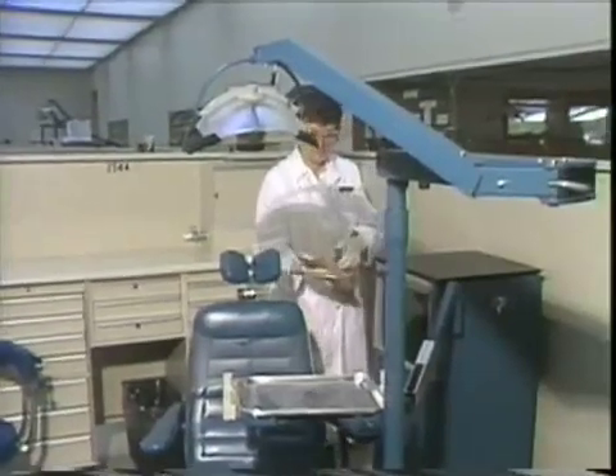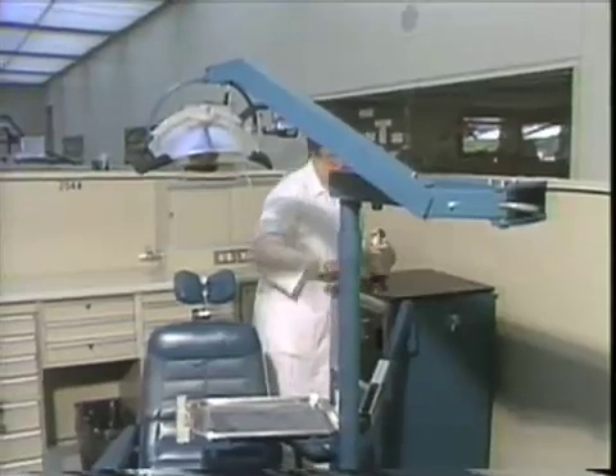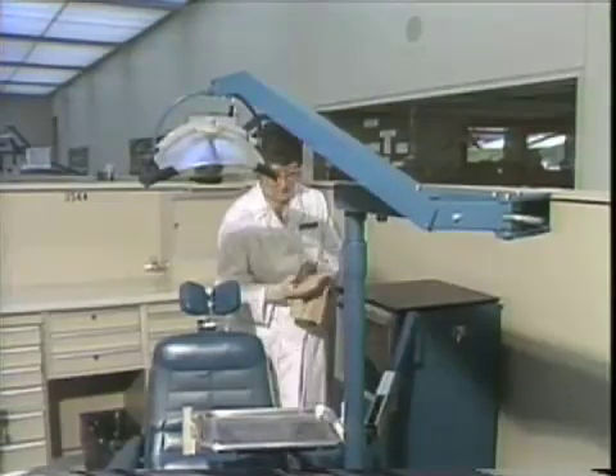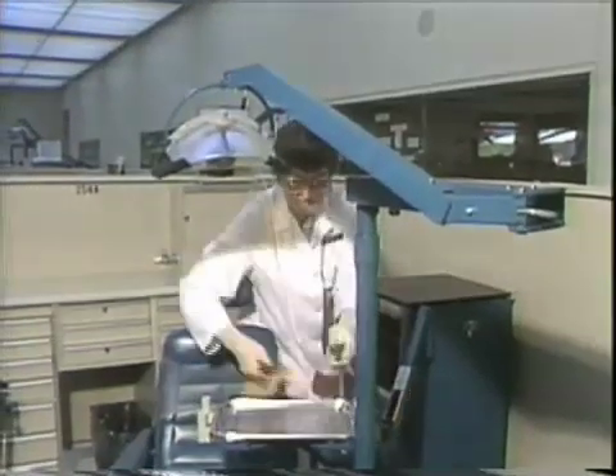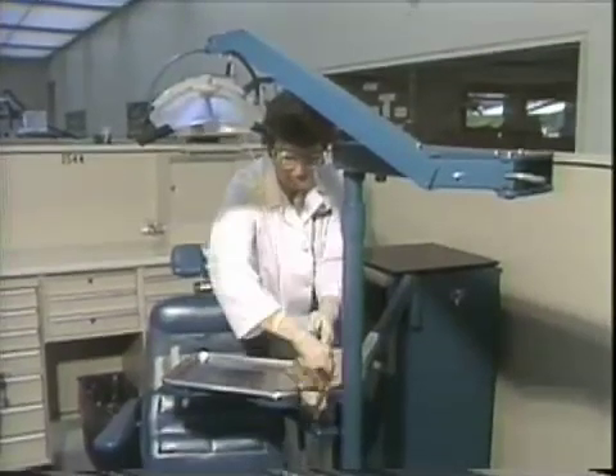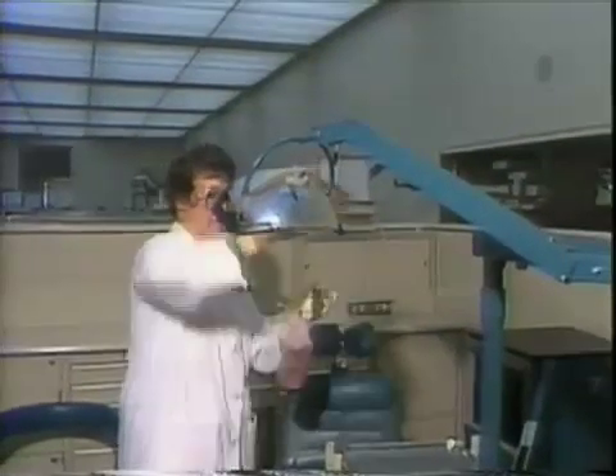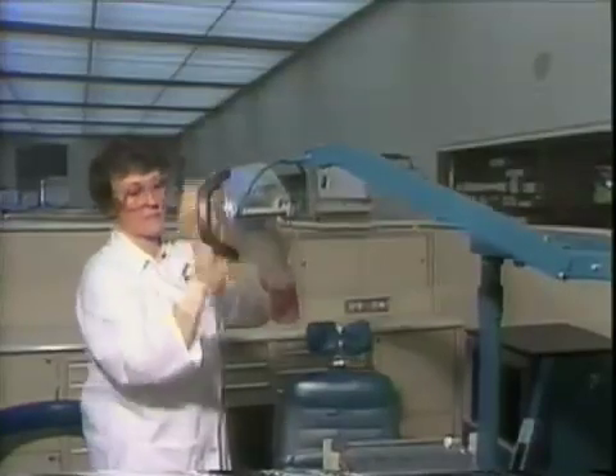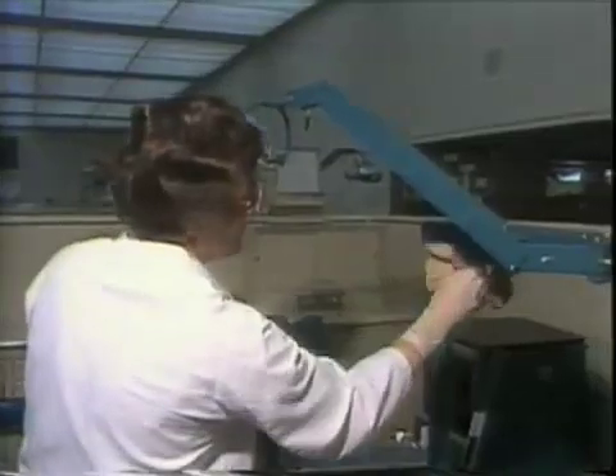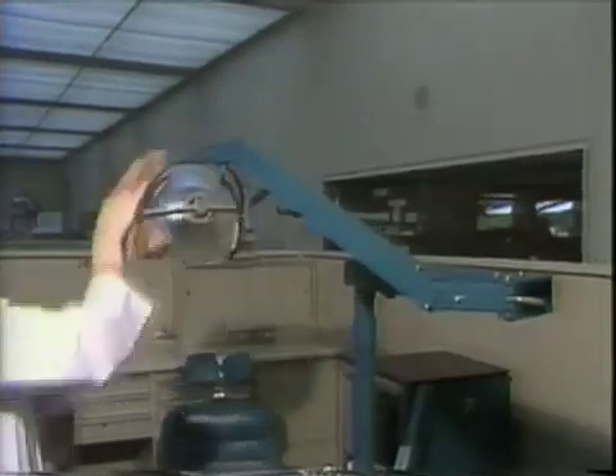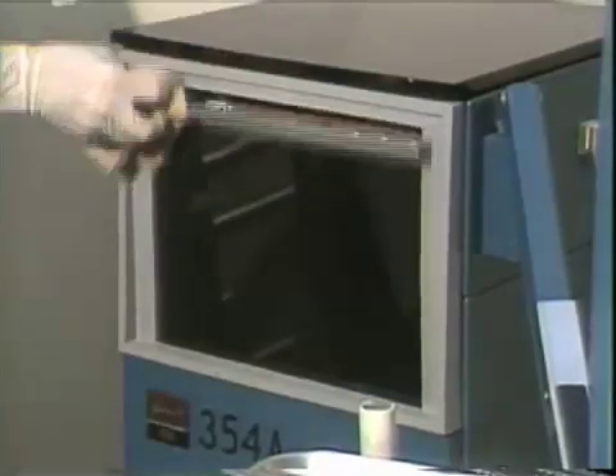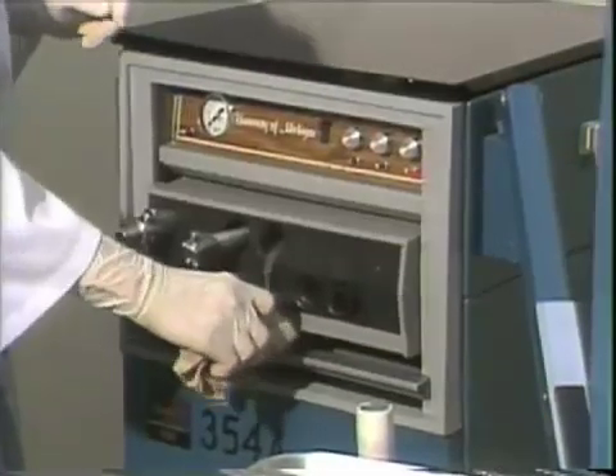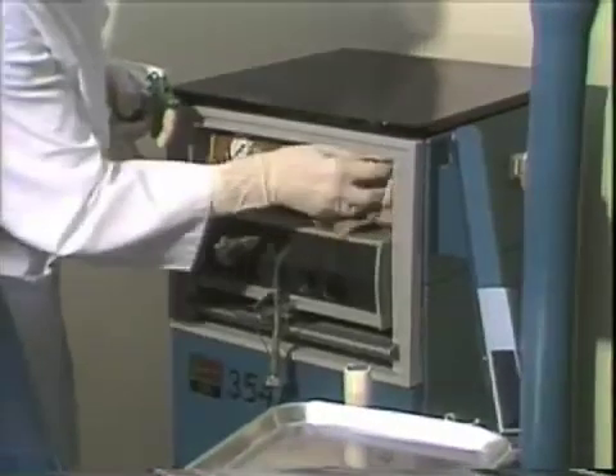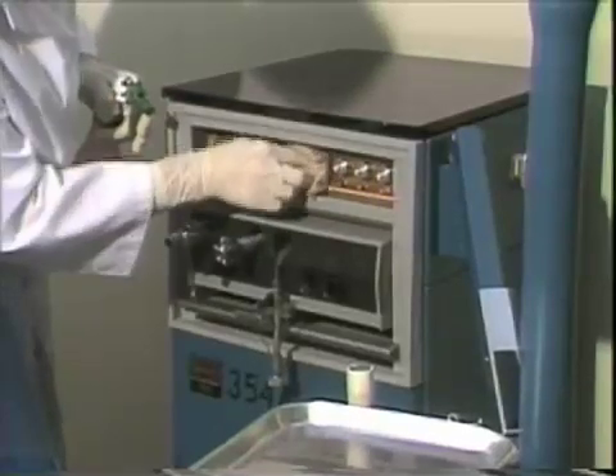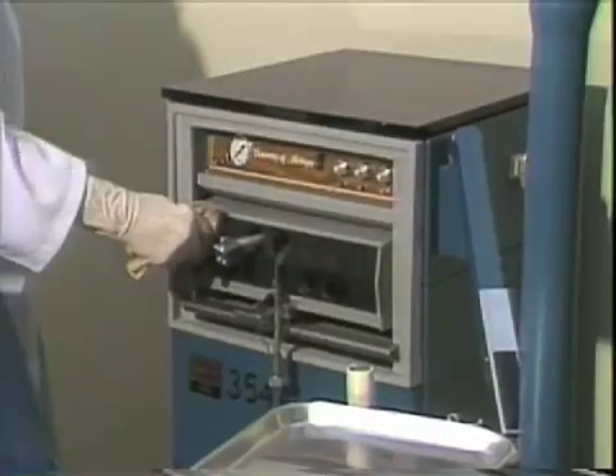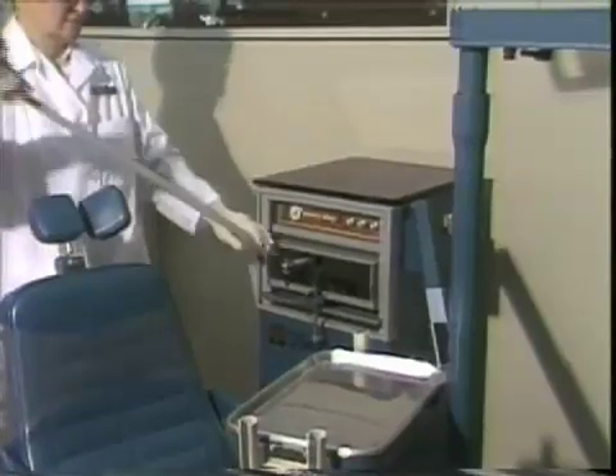Spray the top of the unit and wipe with a paper towel and let air dry. Wipe the following with a saturated paper towel and let air dry: the handle to the instrument enclosure door, the flex arm release lever, the operator's tray, and the instrument holders. Do not spray the dental light. Use a saturated towel to wipe the light handles, plastic cover on the light switch, light intensity control, and let air dry. Wipe the T-handle and pull it out until it locks. Then wipe the control panel. Pull on the connector line to set the brake and wipe with the surface disinfectant.